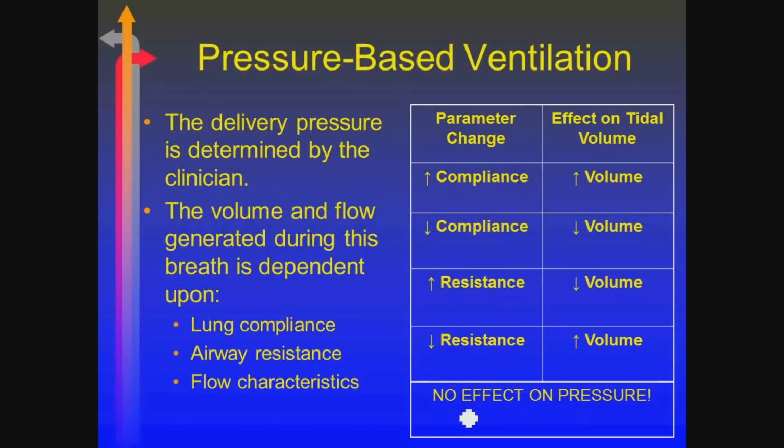This is our IPPB machine. Get a stiff lung, now all of a sudden the tidal volume being generated is less. Resistance is obviously the opposite. What doesn't change in this case is airway pressure, because I'm setting it. It's going to be fixed.